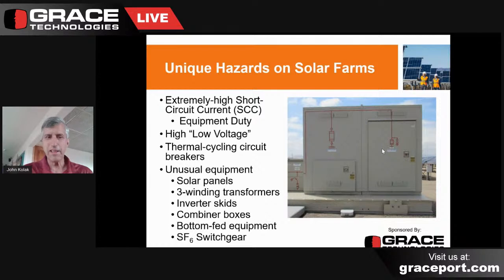Another point that's not directly related to arc flash is that we have unusually high low voltage systems on both wind and solar farms. Before green energy really came into play, we had typically a low voltage system was considered a class 600 volt system. The utilities only warrant that they'll give you voltage within 10% of the nameplate voltage. So give or take 10% of a 480 volt system would be up to 528 volts. And historically, the codes called high voltage systems 601 volts and above. So anything below that was considered low voltage.